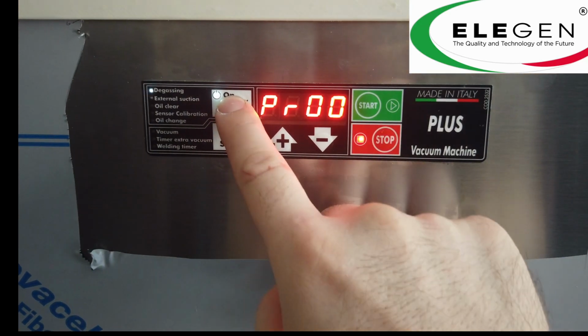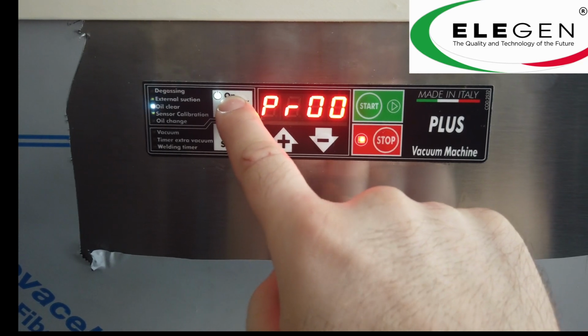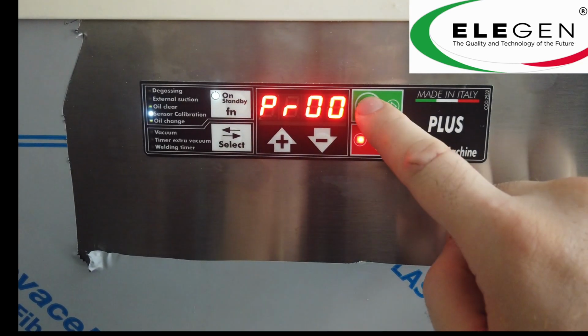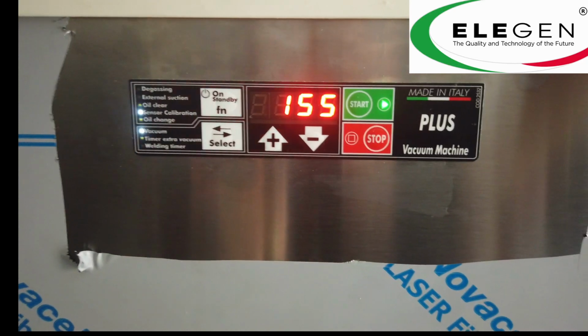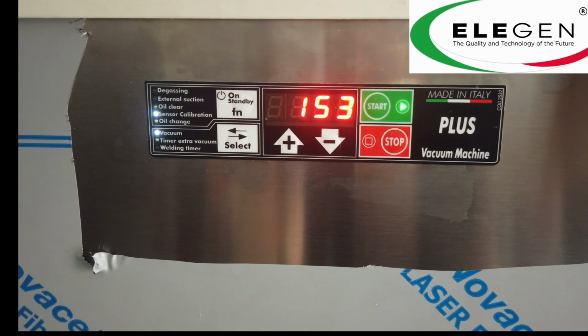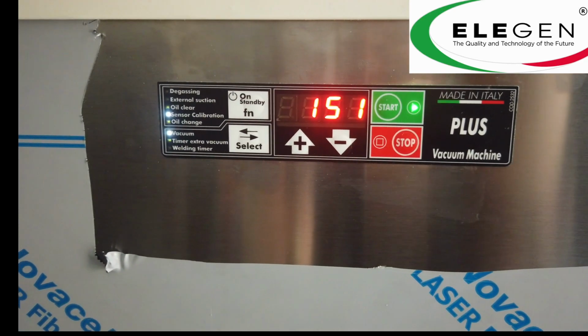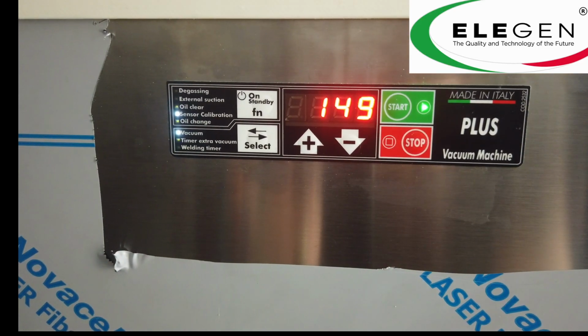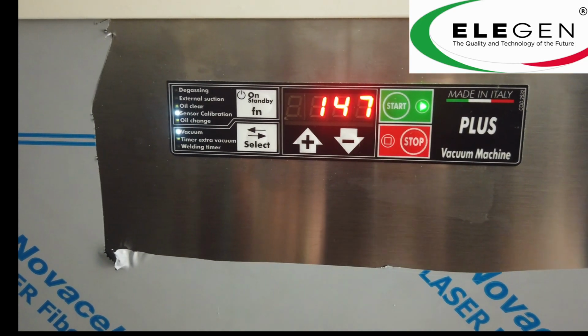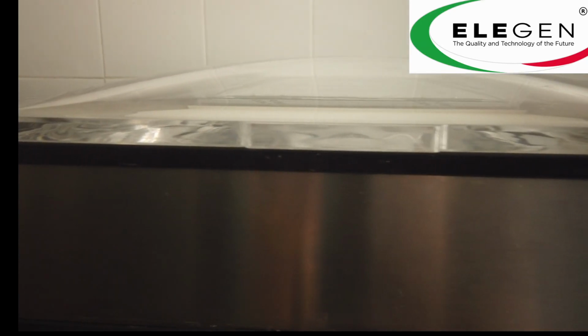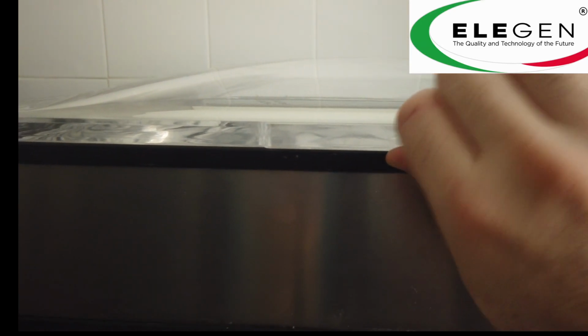To use the machine correctly, it will be necessary to calibrate the sensor. To do this, move with the FN key to the sensor calibration line and press start. The lid must be closed and must not be opened throughout the calibration. Make sure that the cover cannot be opened while calibration is taking place. If you are able to open it, press down slightly to allow the seals to grip.